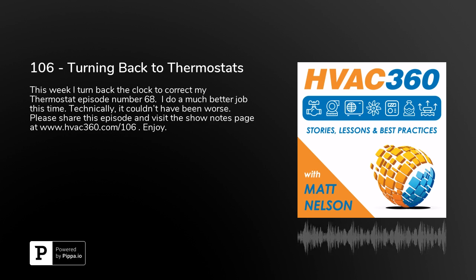So when the temperature rises and it keeps rising, it's going to click on when it reaches that 80 degree set point. And it's going to take the temperature down, and it's going to turn off whenever it gets below that set point. So you're going to make the connection, you're going to break the connection, but when it's going down, when it's decreasing, it's going to break that connection. The fan's going to shut off. So again, it depends on how you're either making the connection or breaking the connection, which way you're actually moving.